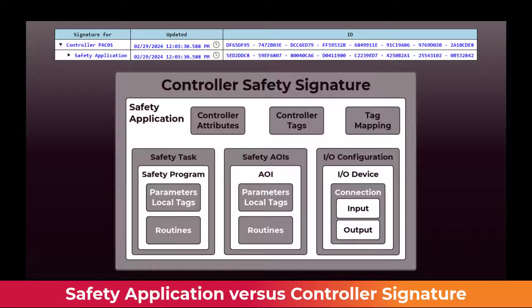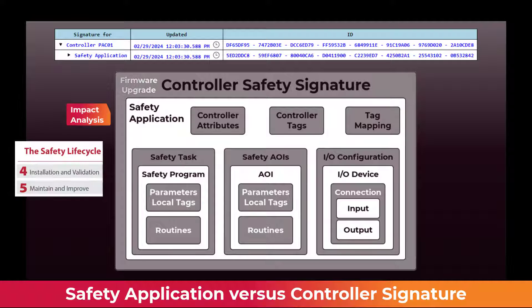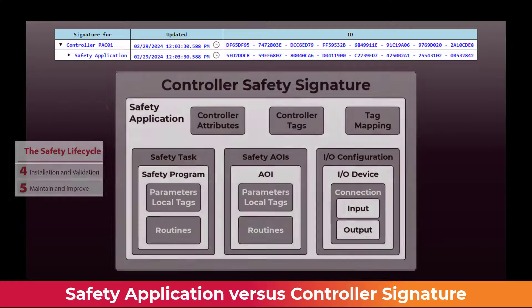The safety application signature appears to be a redundant signature level under the controller safety signature. However, the intent is to have a controller firmware upgrade only affect the controller safety signature. If the firmware does not affect the safety application, the safety application signature can remain the same. An impact analysis could then be used to determine the proper level of validation required for a firmware update.